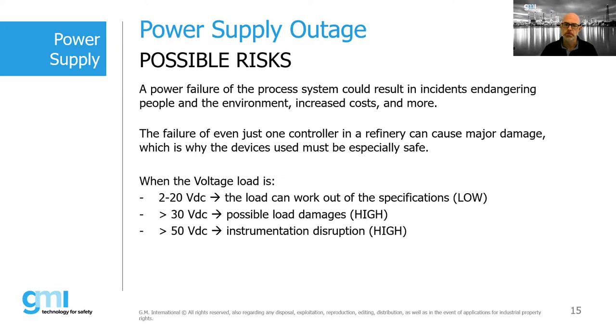Redundancy cannot solve this on its own and cannot guarantee us immunity from power supply failure, because a standard power supply system does not take into account the common faults that can afflict a standard power supply. These common faults can cause spurious system faults with the related production downtime, which would significantly affect cost. And the redundancy of safety power supplies minimizes the risk, because common mode failures are considered in the SIF calculation necessary to get the certification for a safety related device.